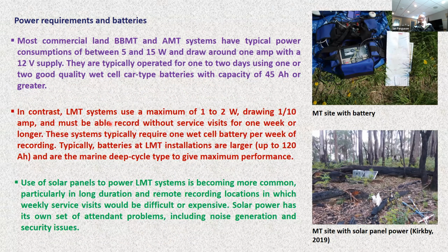For LMT systems, the power consumption is significantly less, typically 1 to 2 watts. And these systems are usually going to require 1 probably higher quality wet cell battery per week of recording.